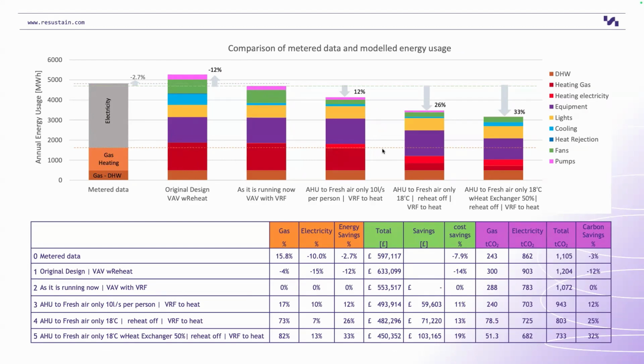This is it running now. Now, if we limit the fresh air to only 10 litres per person, then in the model we can save 12% of the energy. If we set the air handling unit supply air temperature to 18 degrees, we can save 26% of the energy. And then, because I'm a big heat exchanger fan, if we put a heat exchanger into the building, you can go down to about 33% of the energy. So these two things can be done via controls. This would be a retrofit item.